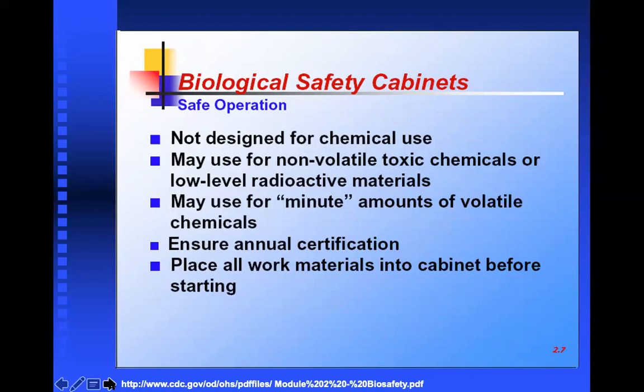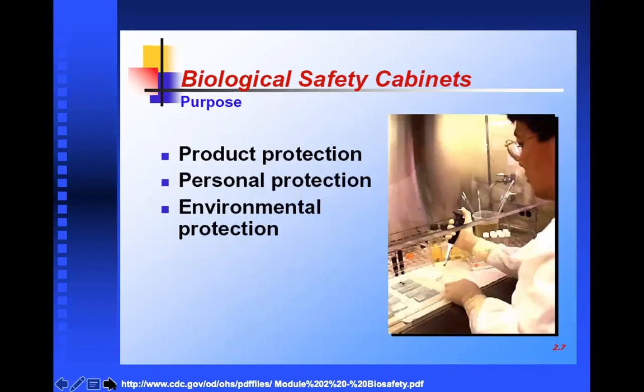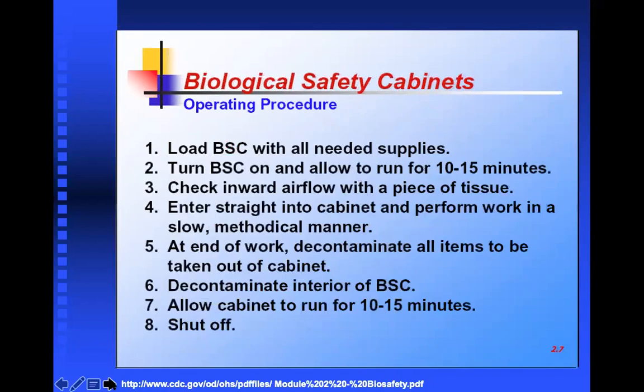It is not designed for chemical use, actually. It may be used for non-volatile toxic chemicals or low-level radioactive materials. It may use minute amounts of volatile chemicals. Ensure annual certification. Place all work materials into the cabinet before starting the job. So you cannot, during working, bring many things from outside and move. No. First, place all the things inside the cabinet. Otherwise you are going back and forth every time.